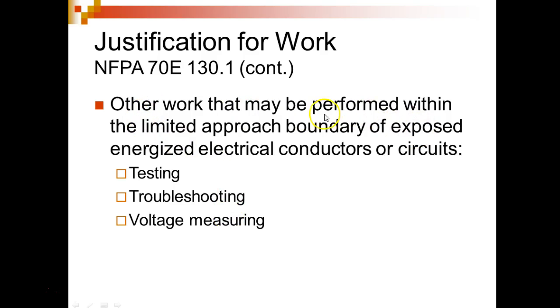Other work may be performed within the limited approach boundary of exposed energized electrical conductors if you're doing what? Testing, troubleshooting, or measuring voltage. You cannot check voltage when the power's off, right? Or you can't check the operation if the power's off. So with testing and troubleshooting, odds are we're going to work on the energized equipment, which means we're going to have to be extra safe. But anytime we do a repair, we're going to lock and tag. Anytime we do maintenance, we're going to lock and tag. When we troubleshoot, we're going to troubleshoot with power on. Everybody, you okay?